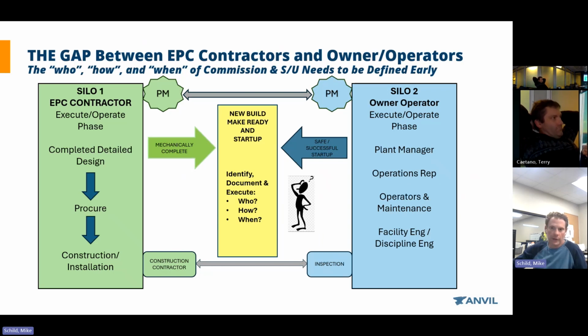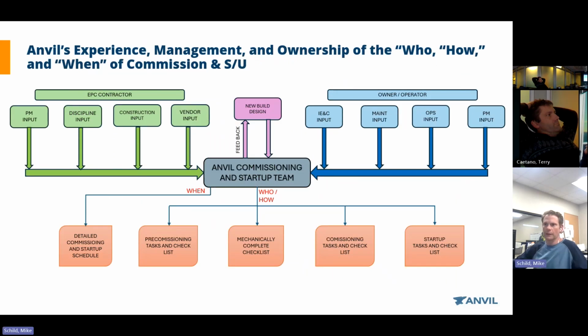They'll bring in vendors that can commission the individual equipment, but integrating all that equipment, you've just brought vendors out to commission to actually start up this plant. There's no plan. There's no task list all the way from going into commissioning and then doing the startup. So that's what we do. We look at it and we want to define the who, the how, and the when. So just high level, just to move this along a little bit.